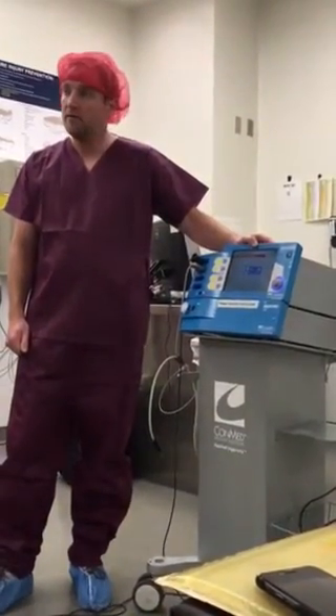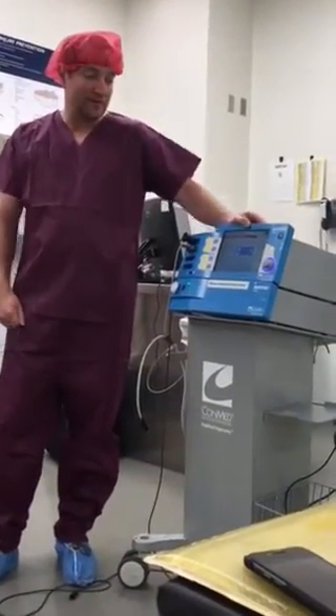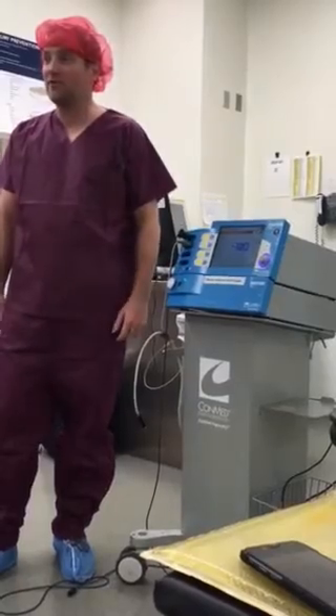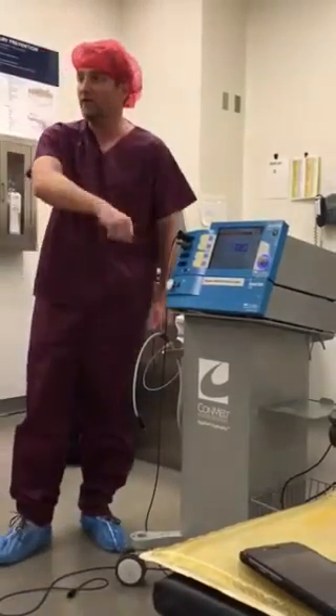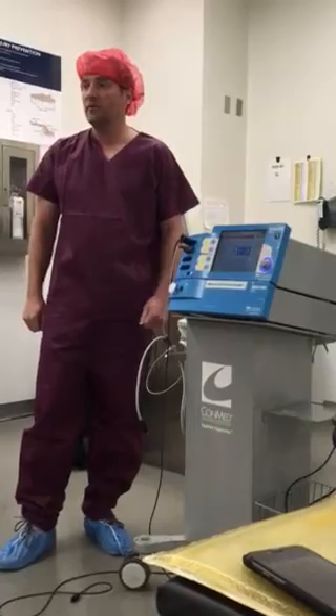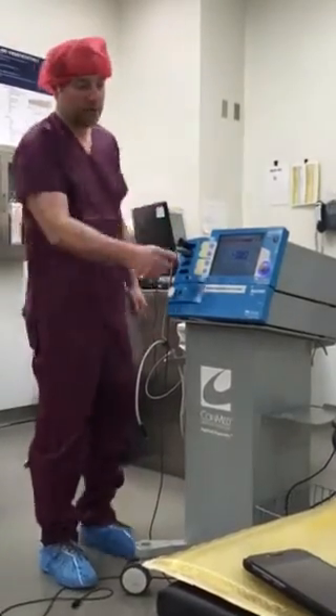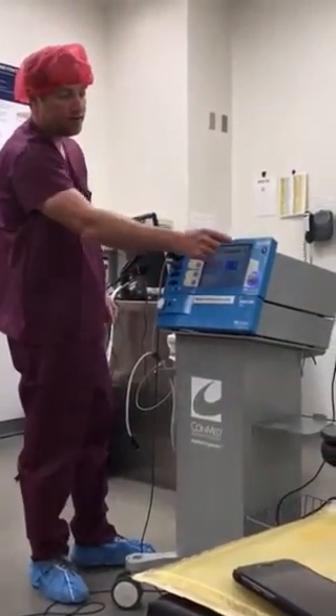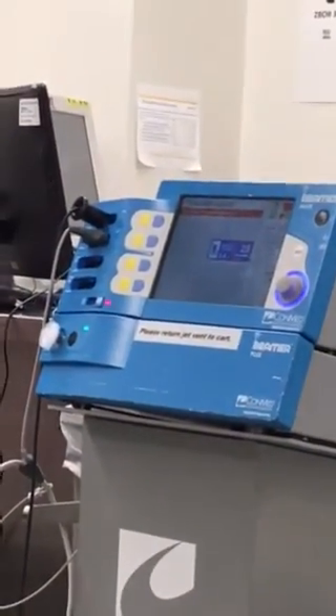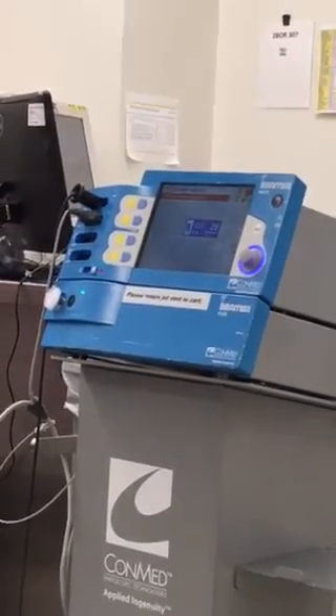Any other troubleshooting? No, basic troubleshooting. I mean, 90% of the time if there's an issue, somebody went in the back and turned off the argon tank. So that's always the first thing you check. You would see, because it would show empty, you have your argon tank right here. It tells you exactly how much gas is in it. Once it comes up with an error, it says no argon. It's usually just somebody turned off the gas in the back.